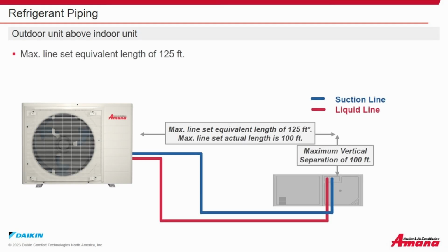Refrigerant piping. When the outdoor unit is mounted above the indoor unit, maximum line set equivalent length is 125 feet, which includes pressure losses from any elbows, bends, etc. Even though the maximum equivalent line length is 125 feet, which includes any bends or fittings, the maximum actual line length is 100 feet. And the maximum vertical separation between the indoor and the outdoor unit is also 100 feet.